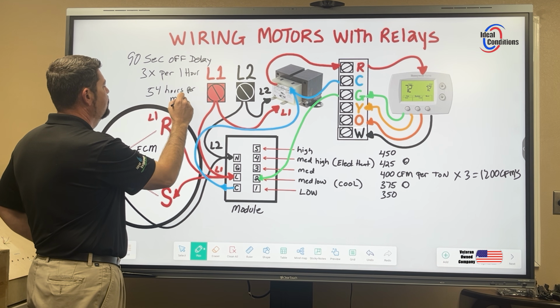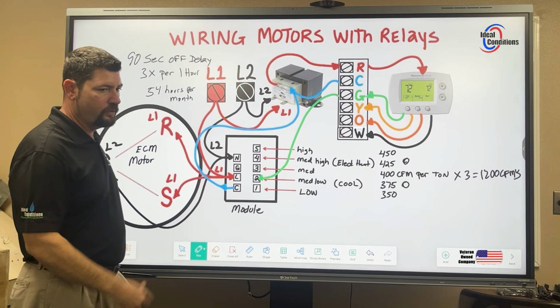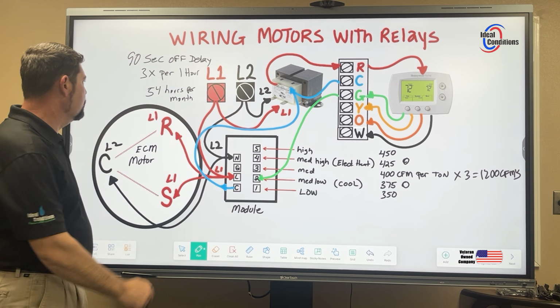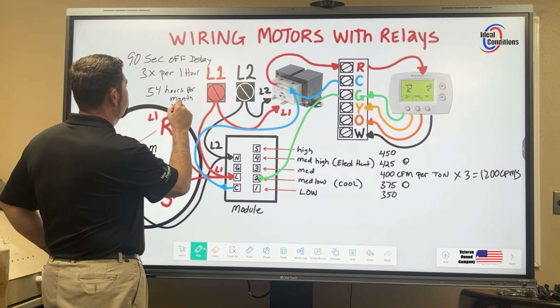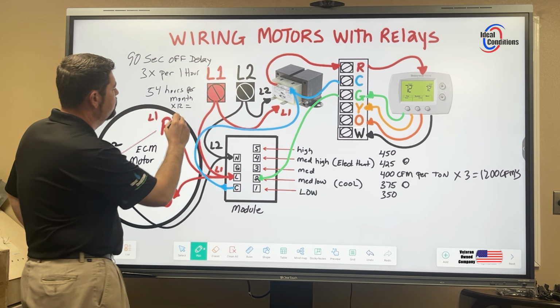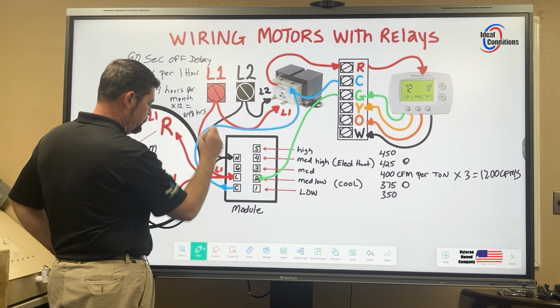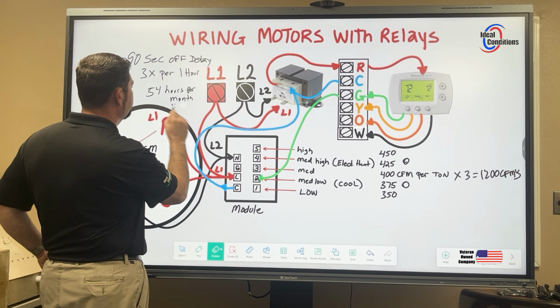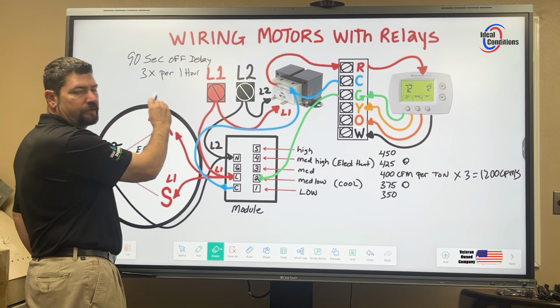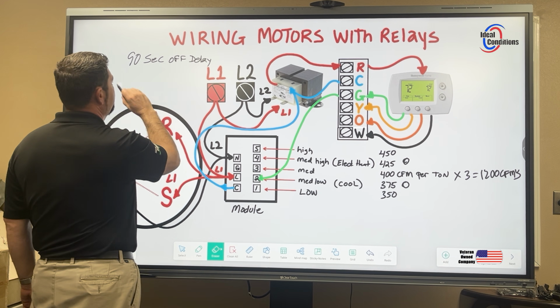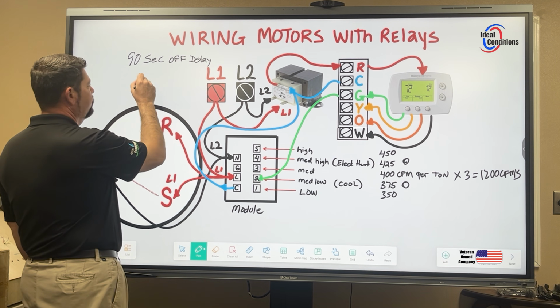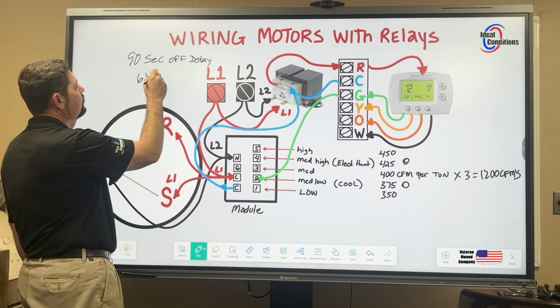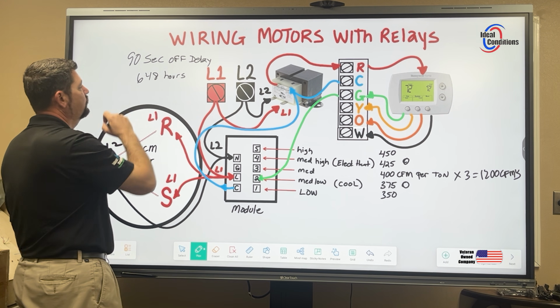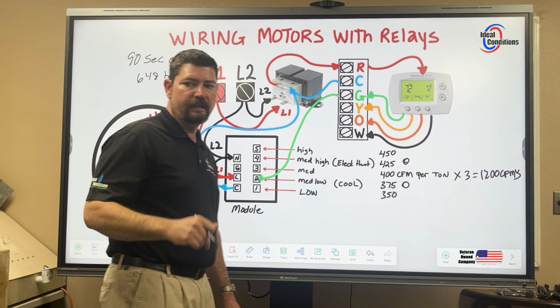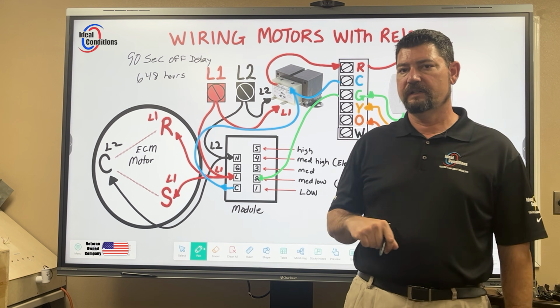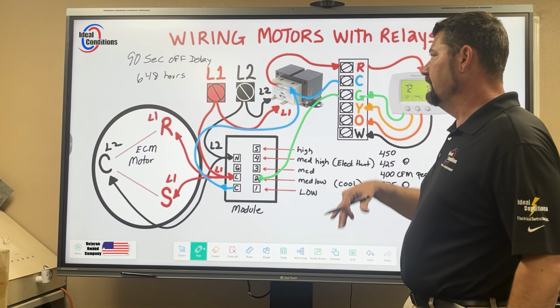And if I wanted to see, in a perfect world, if that was the case, 12 months out of the year, I'd multiply it by 12. 12 months equals 648 hours a year. So let's clean this up a little bit. That 90-second off delay in 1 year is 648 hours. That's a very, very, very long time that off delay is giving you.